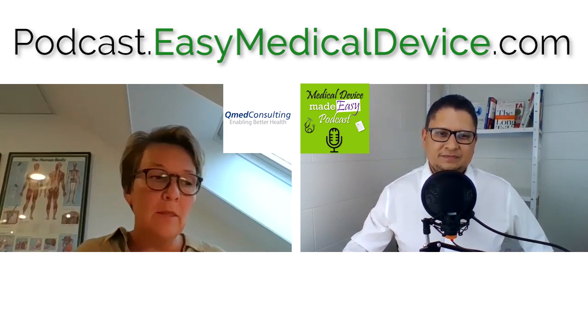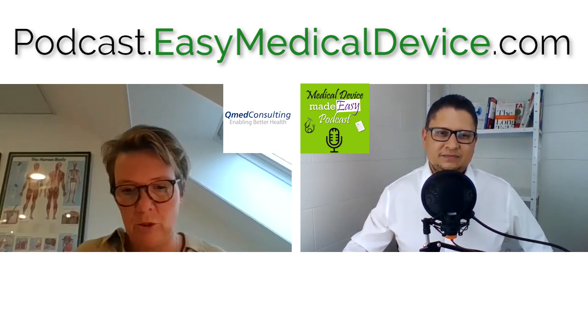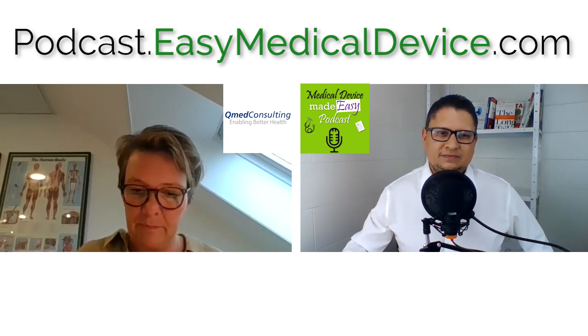Okay. But the best way, and that's what we are all being told, is to go straight into it. Do your documentation. For a low risk class product, it doesn't mean that you don't have to do a clinical evaluation report, and you need to set up your processes according to the MDR. That's one of the things that maybe hasn't really changed, but it's very specific that the notified body and the commission would like you to plan the process and then write your results in a report. And if you change your plans, you need to communicate that to your notified bodies. Don't just sit on it, be proactive.